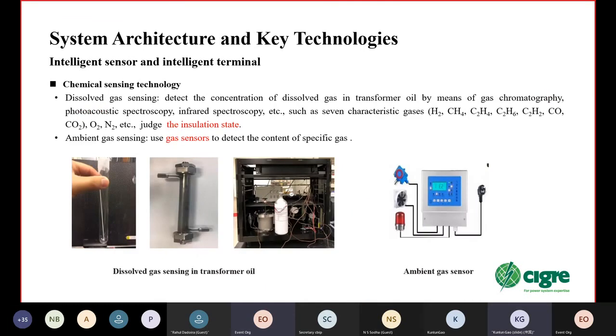Another common sensor is chemical sensing. Dissolved gas sensing detects the concentration of the dissolved gas by means of gas chromatography, photoacoustic spectroscopy, and infrared spectroscopy, for some gases such as H2, CH4, C2H2, etc., to judge the insulation state of the equipment. An ambient gas sensor uses a gas sensor to detect the content of a specific gas in the air.